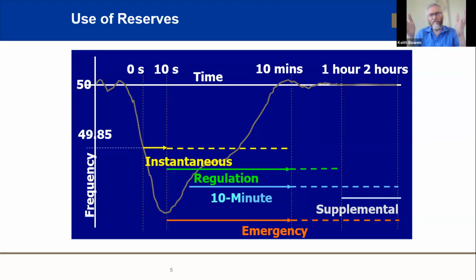That instantaneous reserve, the phrase we use in the South African grid code, is essentially the primary reserve. Then we have the regulating reserve, which is generally there for managing load following and trying to keep frequency within the band. It also kicks in when there's an incident, a little later than the instantaneous reserve, with pulses coming from the central system to get generators and other suppliers to pick up. A bit later, the 10-minute capability kicks in - that's our pump storage and other generators that are online but not as fast to respond. You can get a lot more energy out of them over 10 minutes, and they help restore the previous reserves.